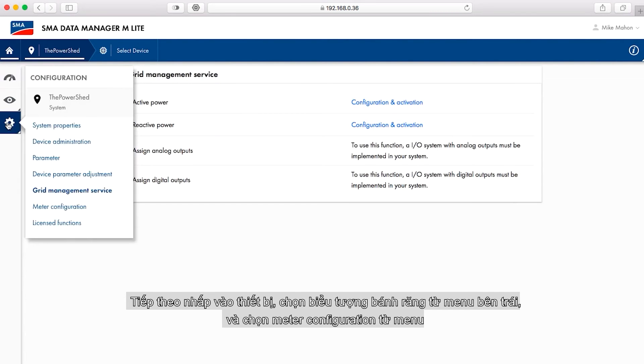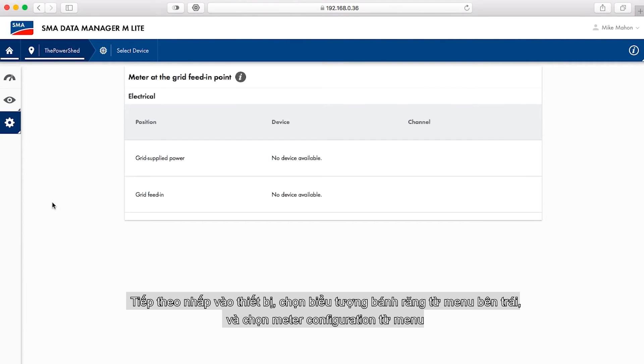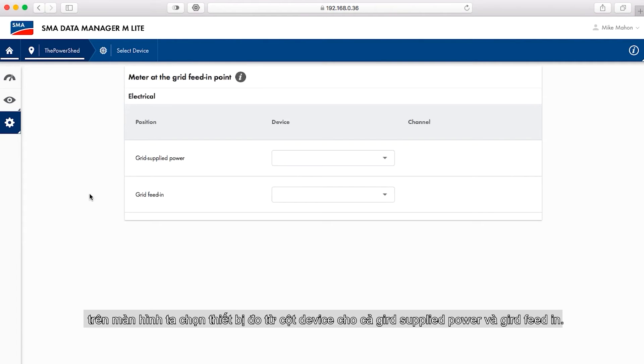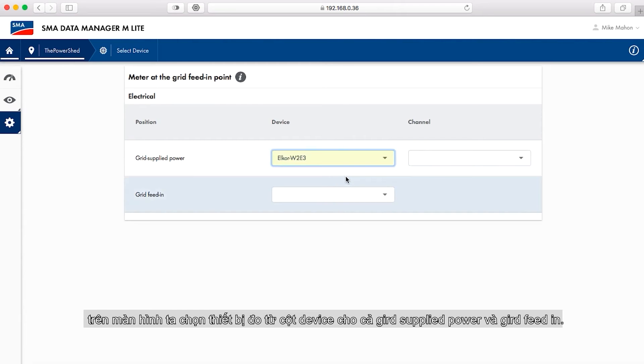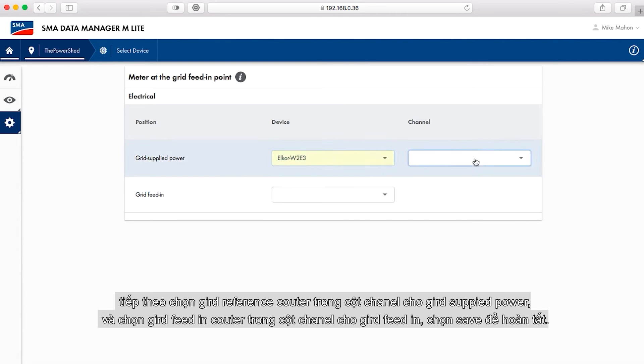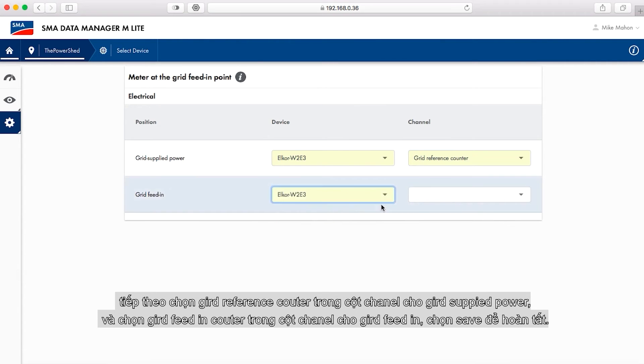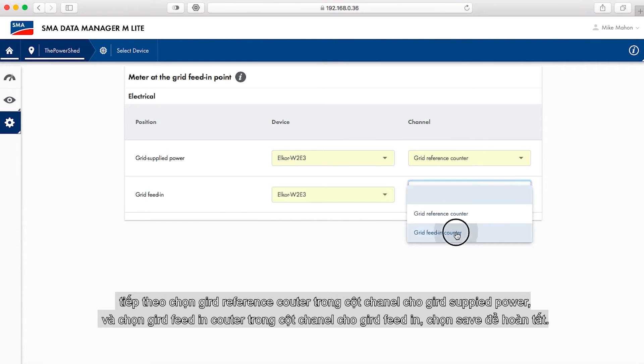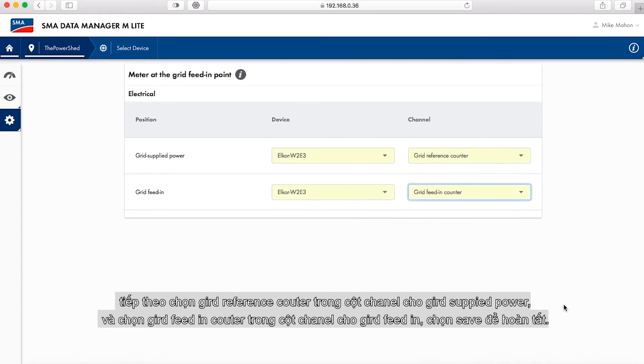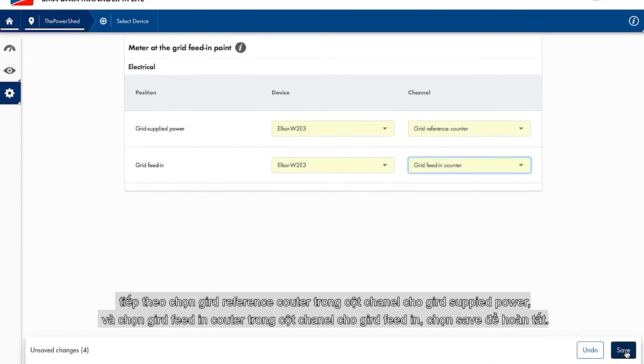Select the configuration icon from the menu on the left and select meter configuration from the menu. On the screen that appears, select the meter in the device column for both purchased electricity and grid feed-in. Select grid reference counter in the channel column for purchased electricity. Select grid feed-in counter in the channel column for grid feed-in. Click save when done.